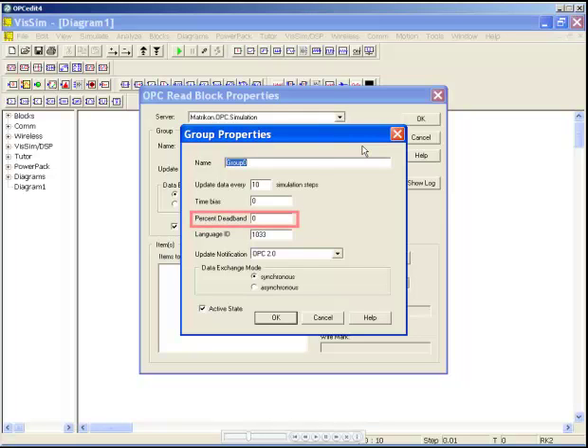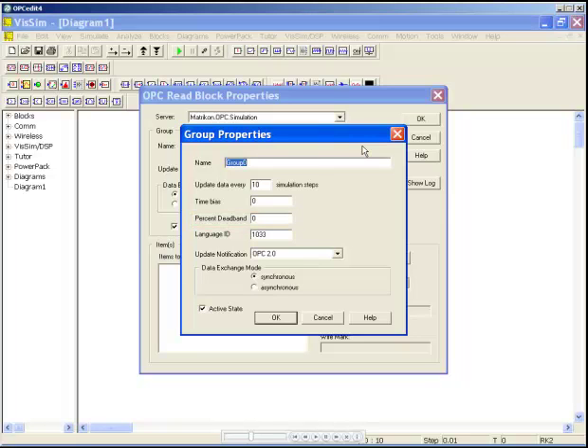Some OPC servers have dead-band support for updates from analog data sources. The dead-band value is a percentage of full-scale deflection. If you do not know the high and low limits for the items ahead of time, keep the default value for this field.